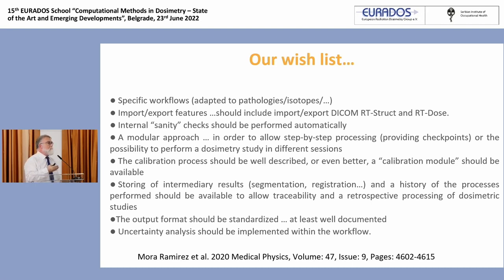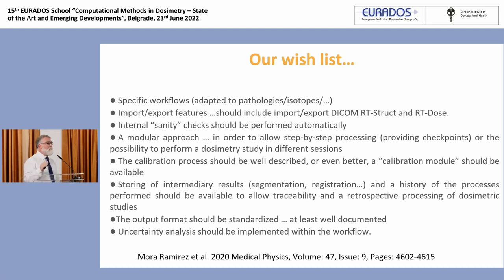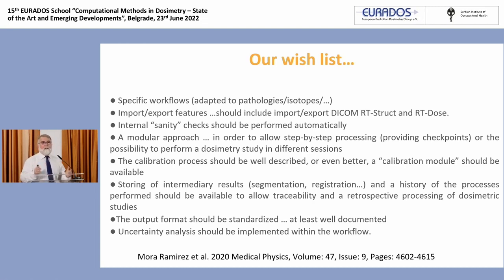We want a modular approach because that's how it's done, and we want the modules to communicate. We want the calibration process to be described — at the moment it is not. Some software ask for a calibration factor in MBq per count, others in MBq per count per second, or counts per second per MBq — you can have exquisite mistakes depending on how you input your calibration factor. In a previous IAEA project just completed, that was one of the main causes of error. Also: storing intermediary results, well-documented output formats, and uncertainty analysis — that's a fantasy but important.